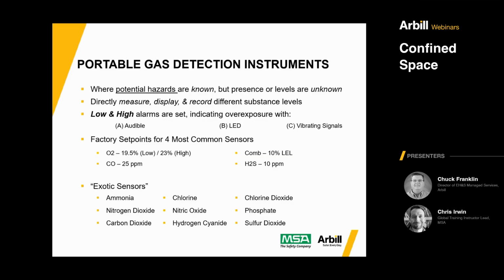At the bottom here, it mentions exotic sensors. We do run into some cases where other things need to be tested for—exotic sensors such as ammonia, common in refrigeration, chlorine for something like sewage treatment, and sulfur dioxide, common in chemical facilities or processing of oil derivatives, oil and gas. So we sometimes need other sensors. Those can be bought and even put into the detector afterward if you know you need something beyond what the normal detector is set up to detect.